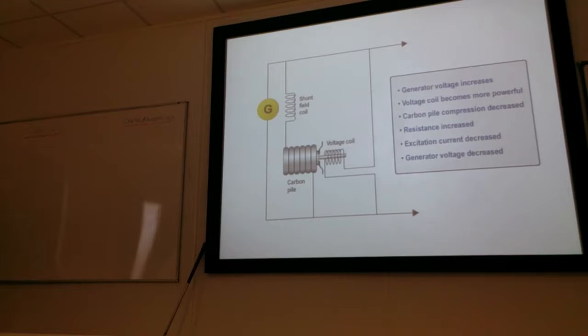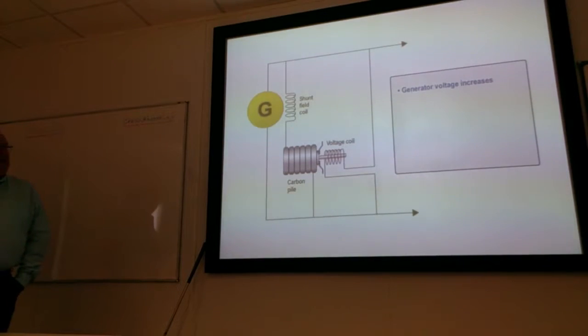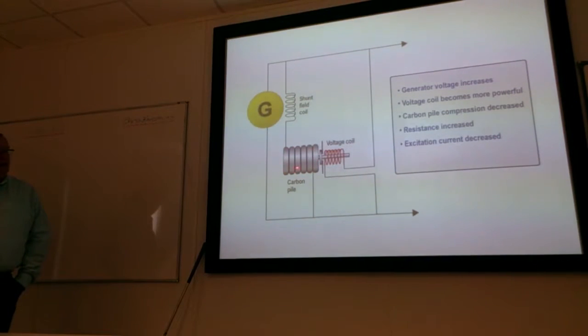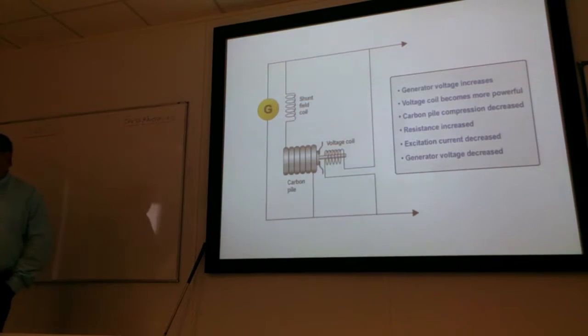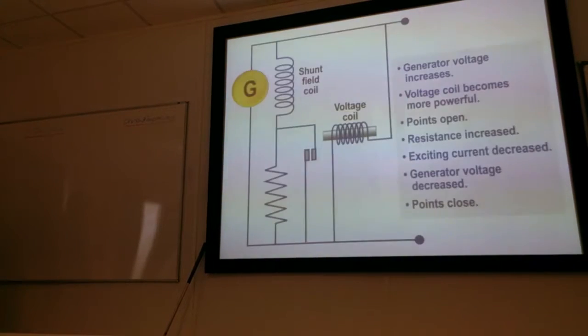Okay, the generator voltage increases. The effect of that is that the voltage coil here becomes more powerful, and that magnetises here, so this is like a solenoid. The compression on that is relaxed, which increases the resistance, which decreases the current through the excitation coil, which in turn decreases the output of the generator. Simple. Old-fashioned, still works.